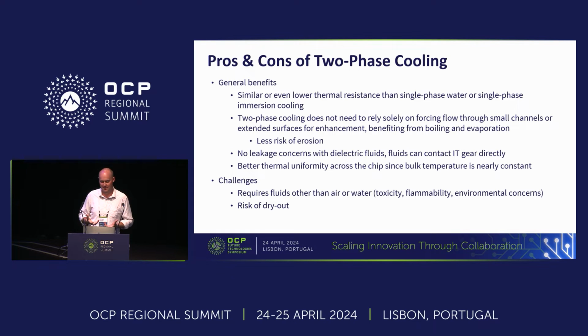If you don't have an expertly designed solution, there's a risk of dry out. If for some reason there isn't enough liquid at the chip to boil, not only does performance degrade, it becomes one of the worst forms of heat transfer, almost approaching air cooling, which is not good.